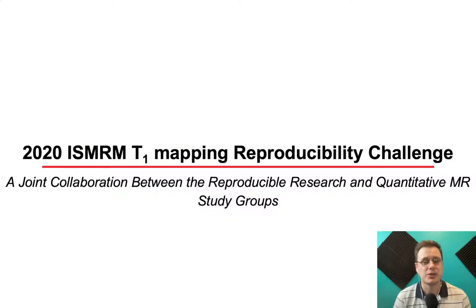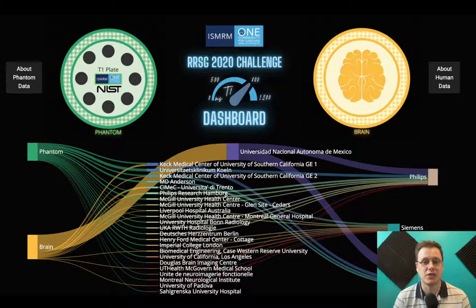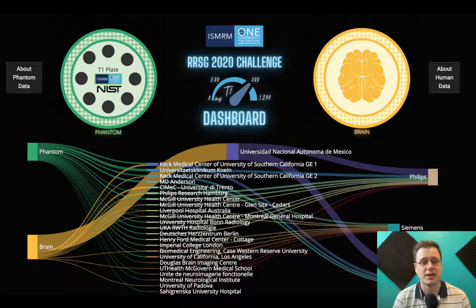Finally, I just wanted to briefly touch on the 2020 ISMRM reproducibility challenge, which I led and focused on T1 mapping. The challenge pitched for that year was: will an imaging protocol independently implemented at multiple centers reliably measure what is considered one of the fundamental MR parameters, T1, using the most robust technique, inversion recovery, in a standardized phantom — the ISMRM/NIST system phantom? Overall, we received 19 submissions containing a total of 41 phantom datasets and 56 human datasets.